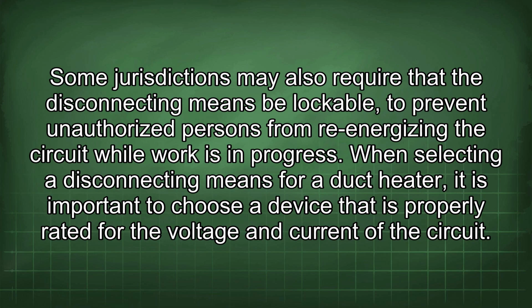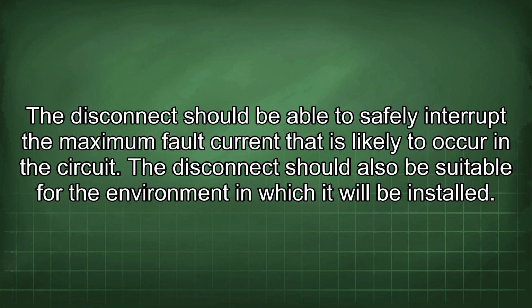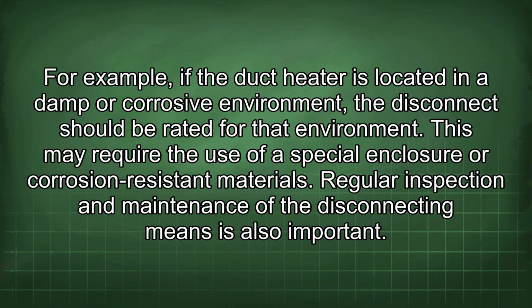work is in progress. When selecting a disconnecting means for a duct heater, it is important to choose a device that is properly rated for the voltage and current of the circuit. The disconnect should be able to safely interrupt the maximum fault current that is likely to occur in the circuit. The disconnect should also be suitable for the environment in which it will be installed. For example, if the duct heater is located in a damp or corrosive environment, the disconnect should be rated for that environment. This may require the use of a special enclosure or corrosion-resistant materials.